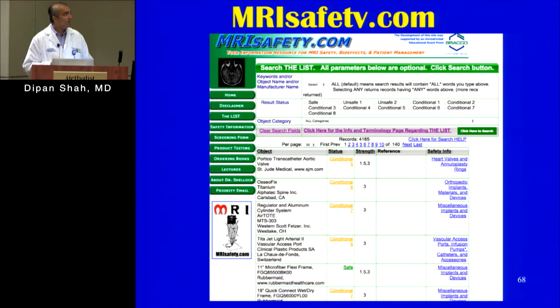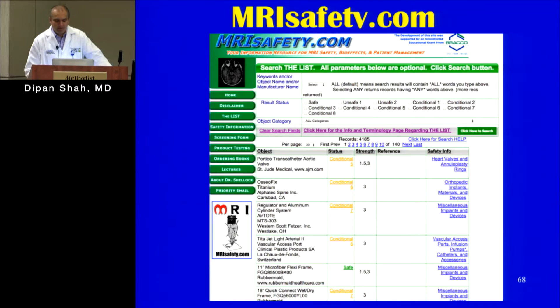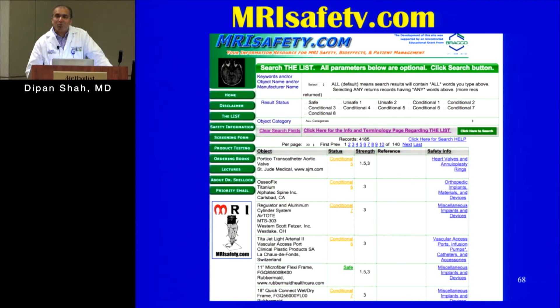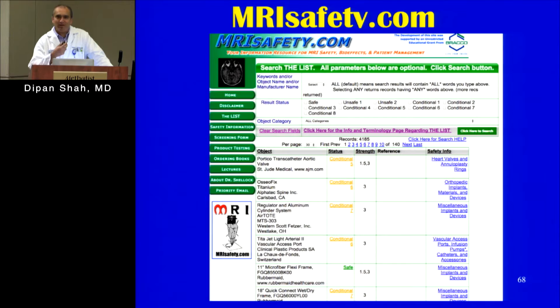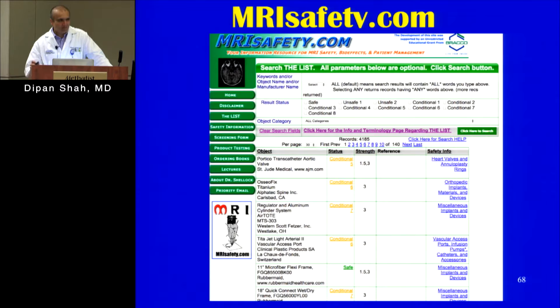I recommend the website mrisafety.com — if you're caring for a patient who needs a scan but has some kind of device, you can enter the device name and it will tell you what scenarios it's been tested in and its labeling. It may say safe or, more commonly, conditional, listing the specific conditions tested — for example, at 1.5 and 3 tesla, or for outside-chest versus total-body imaging. The most important message: with any device, it's conditional for a specific set of circumstances. If there's ever a question, look it up.